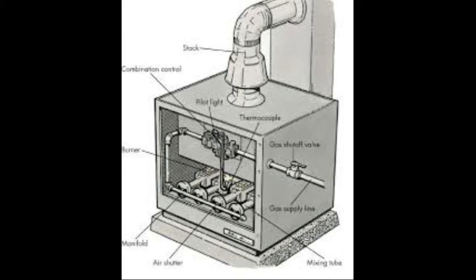Gas furnaces populate the largest portion of homes today. These furnaces operate by burning natural gas consisting of both methane and other carbon-based gases. The igniter within the furnace turns on when the thermostat in the home registers below a preset temperature. Gas begins to flow into the furnace through underground pipes, and the igniter then lights the natural gas, creating several flames that heat a set of metal tubes known as a heat exchanger within your furnace. The heat exchanger is the part that the cold return air will flow over and become warm before the blower sends this air to the vents throughout your home. Because the gases are flowing into the heat exchanger in this process, a cracked or damaged heat exchanger can cause carbon monoxide, an odorless, tasteless, deadly gas, to enter your home.